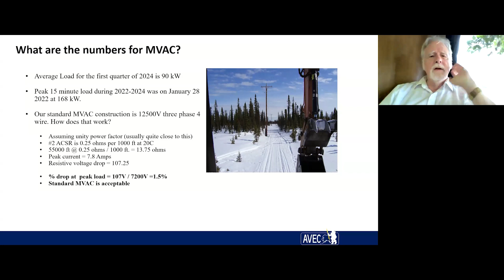So looked at the numbers again, and Darren was talking 25 kV, but I do know that the cost of the inverters goes up with the terminal voltage. So I just did a calculation at 10 kV DC, in order to find out if this standard number 2 ACSR construction would be serviceable. I also assumed that since we had 4 runs of wire total, that we'd run out 4 wires. At 25 kV, that's not possible, or not necessary. But with 10 kV, I'm trying to reduce the resistance loss.